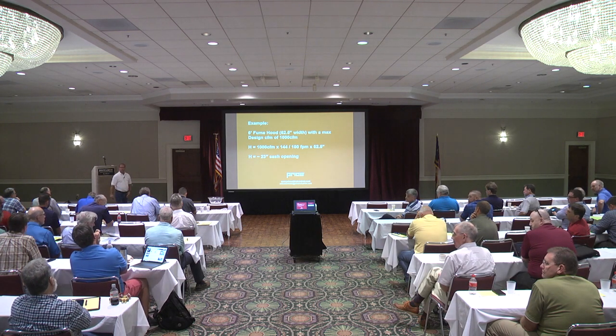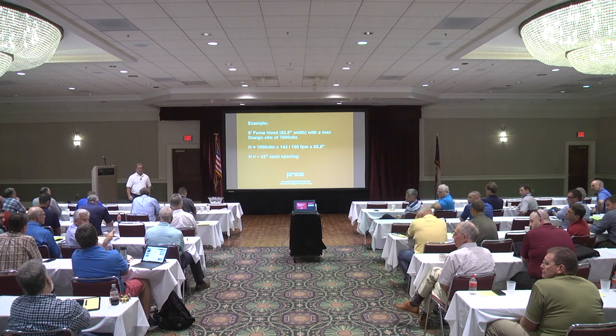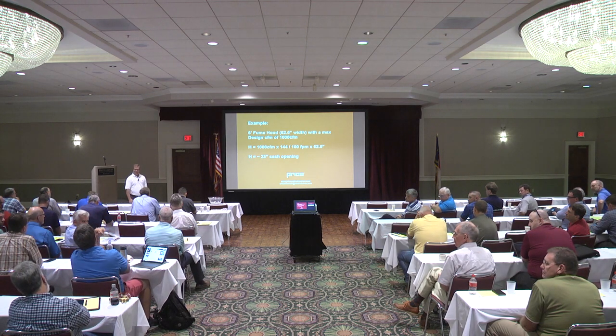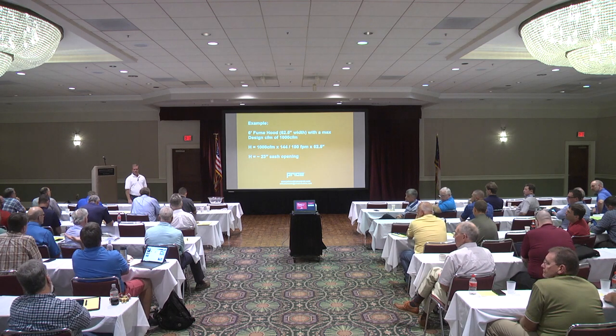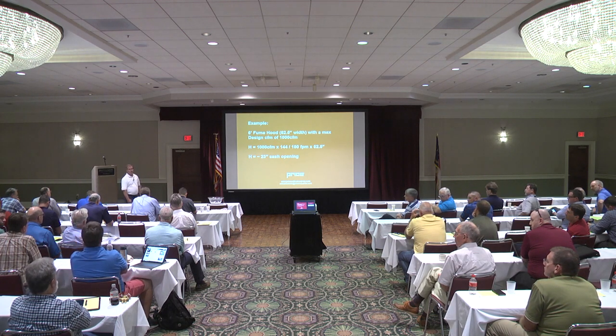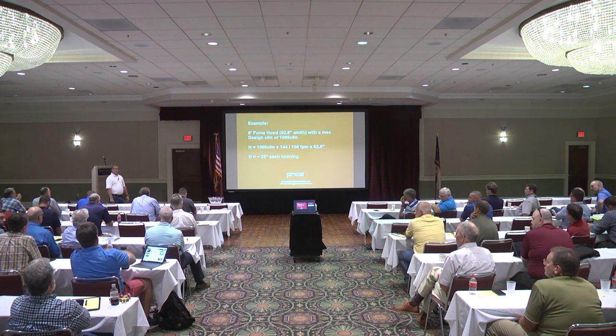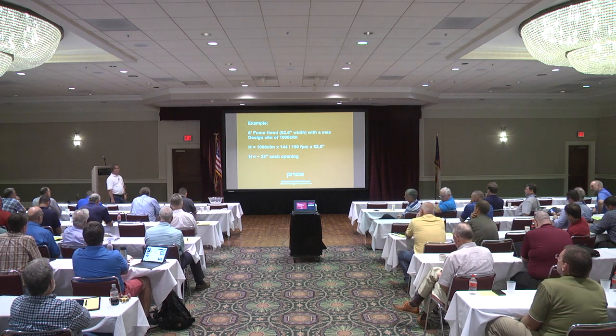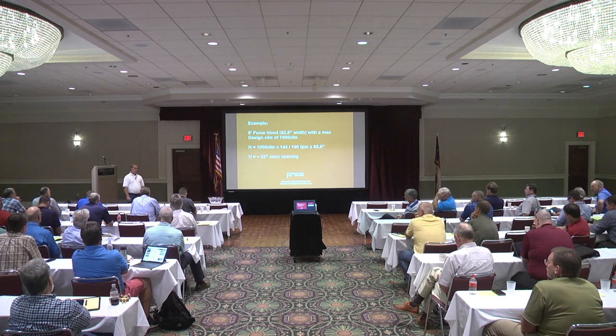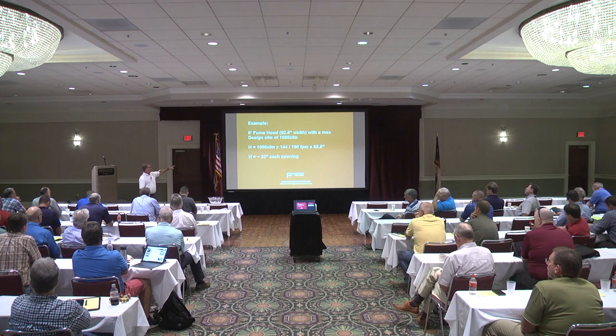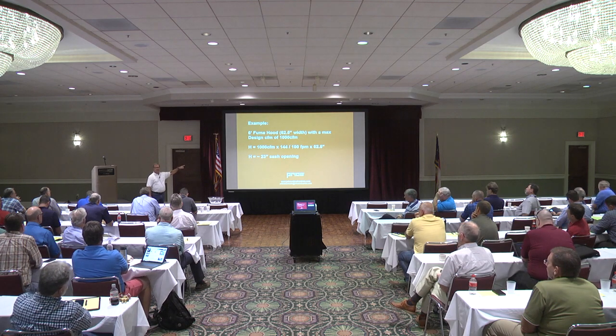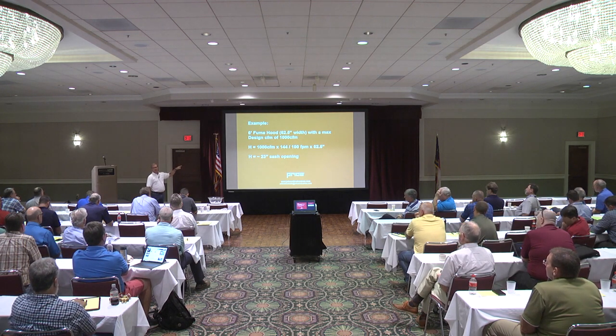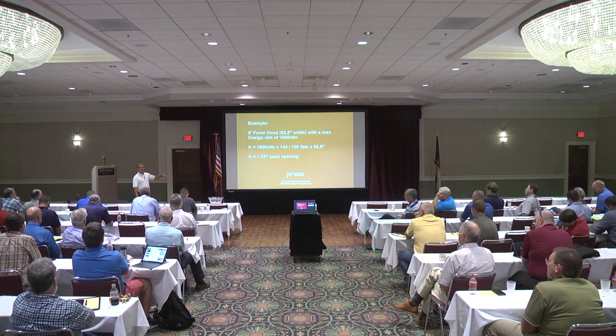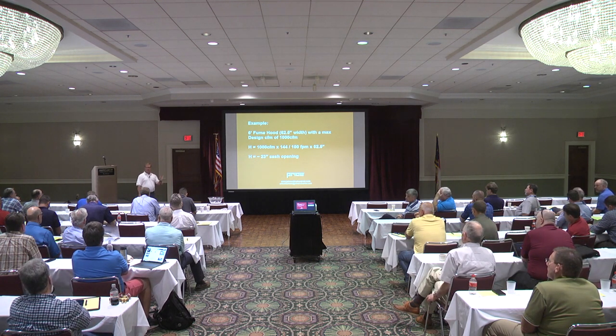It sounds like this is solely talking about flow measuring lab hoods though that are reading feet per minute. That's exactly what this is referencing, and that's the essential difference right there, as opposed to just a constant volume hood where you're going to set it. Feet per minute or whatever cycle. These are variable volume fume hood requirements. A constant volume, that's a known CFM. You're going to use the same equation to calculate the velocity. The unknown now is the velocity, where in a VAV hood, the velocity is known as a constant.